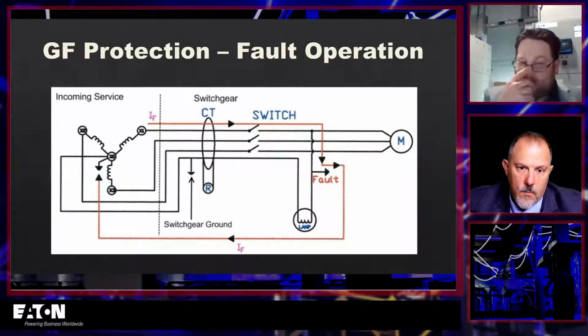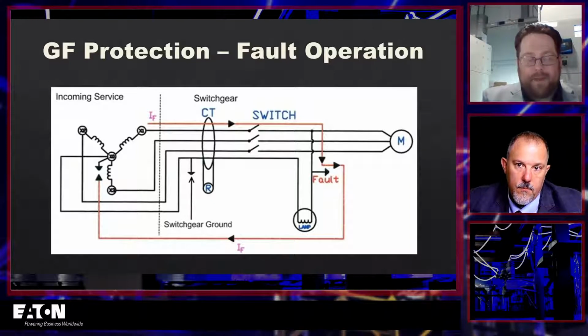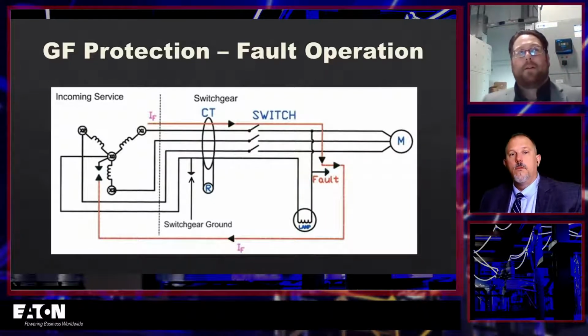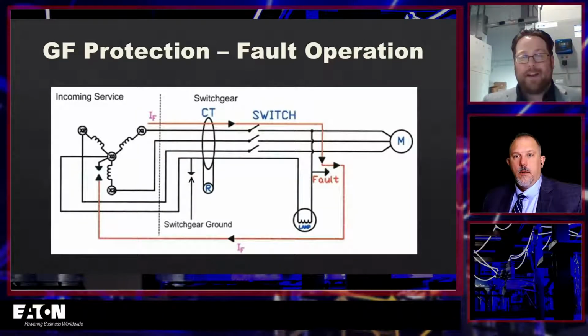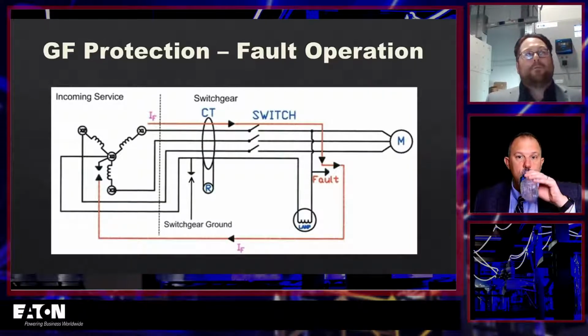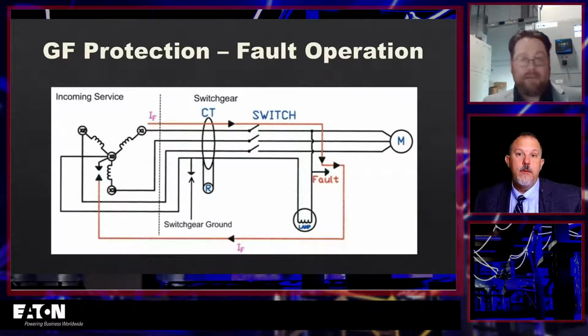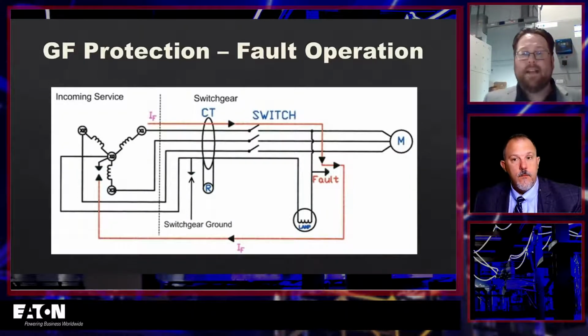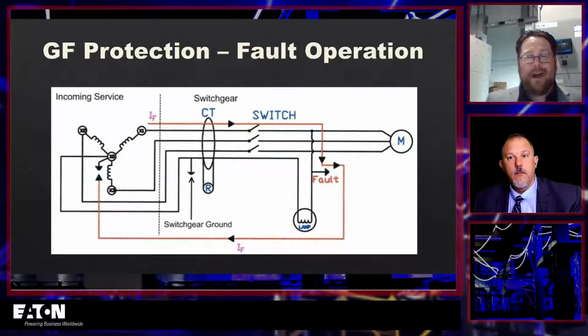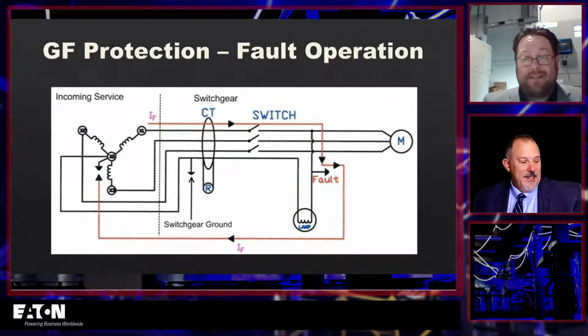Yeah, I was just saying, I think this is actually a great thing I just thought of as we were looking at this chart here. You were talking earlier about the time delays we put in the phase protection, right? And we do that in the ground protection also. But how resistive is this fault when you think of it literally traveling through earth? Maybe your facility's cement, dry cement is actually a relatively decent insulator, honestly. So this fault current might not be of the magnitude that the phase protection ever even sees it. It may be below that phase protection, or it may take hours for the phase protection to operate. Goes back to your fires.